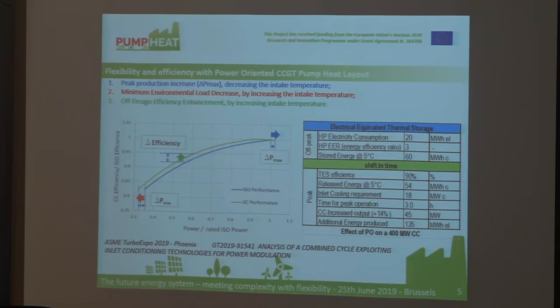This is a simple example: we can absorb 20 megawatt-hours of electricity during the low price period. With a coefficient of performance, or energy efficiency ratio, of 3, we can store about 60 megawatt-hours of cold energy. With some storage efficiency, we can release this energy for a power boost, getting an additional 135 electrical megawatt-hours produced.